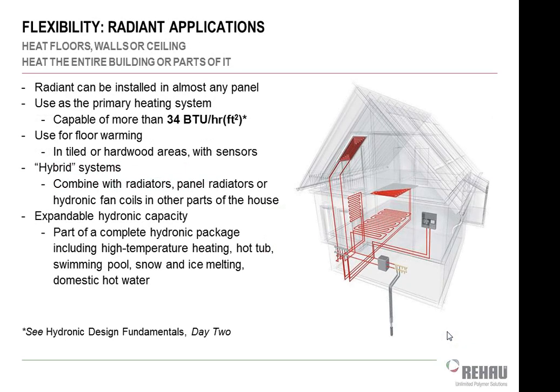So we can put this radiant tubing pretty much anywhere. The best place to put it, especially for new construction, is in concrete. Ideally, you can do that in the basement floors or the slab floor on a commercial building. That's very easy to do. If you want to put it in as a retrofit, we do what we call staple-up systems very often, where we'll go underneath the wood floor in, say, your kitchen or your bathroom, and staple the tubing to the floor there, and then put insulation underneath that with aluminum foil facing to keep the energy deflected upward.